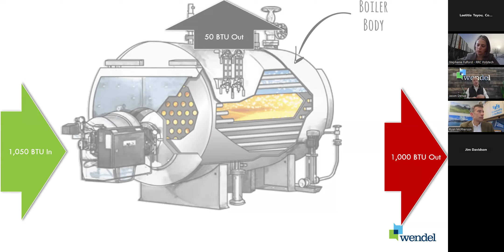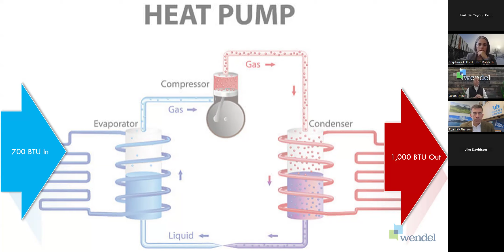So then let's talk about a heat pump. Well, a heat pump is different. A heat pump by its nature transfers energy. So in order to get that 1,000 BTUs out, it's going to absorb 700 BTUs from somewhere. That somewhere could be a chilled water loop. That somewhere could be the ground through a geothermal system. That somewhere could be air. It's going to absorb 700 BTUs from somewhere, and it's going to have a compressor that's being acted upon by electrical utility input energy, about 350 BTUs, to create that 1,000 BTUs out. So it's not generating energy the same way a boiler does. It's actually transferring energy from one area to another. And the key thing to understand here is that the input energy for the current boiler is about 1,200 BTUs of energy coming in to get that 1,000 BTUs out.